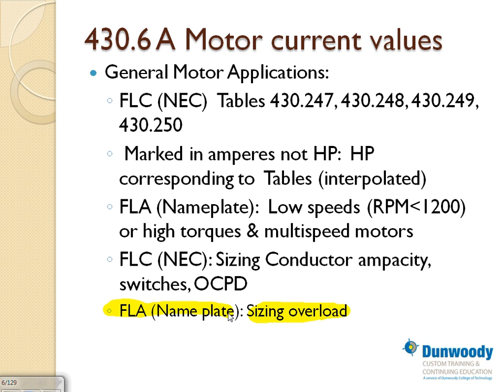And anybody wonder why? Why do they want you to use the nameplate full load amp to size the overload? Because the overload is very important, guys. It can smoke your motor. If you don't size the overload right, it could smoke your motor. So they don't want to depend on the NEC code book full load. They want you to use the manufacturer specific full load amps for the overload. Any comments? Any questions? I hope I'm not going too deep into that one.